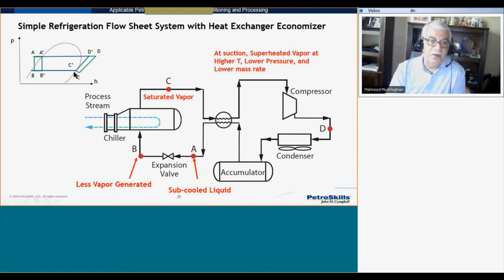But here, because of the pressure drop, we go down, because on the y-axis, pressure, and temperature shift to the right because temperature increases. So the net effect is the power requirement goes up compared to a simple refrigeration system.